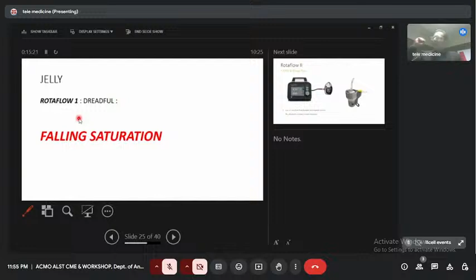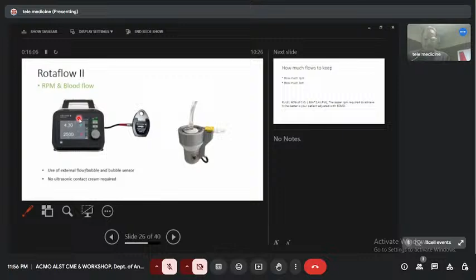is recently used at most of the places, but still, till date, Rotaflow 1 and that previous Cardiohelp is also used. But from now onwards, most centers will have this Rotaflow 2. It has this external flow or bubble sensor and detector that helps us to read the flow of the blood. It doesn't need that jelly part. So they have innovated a new technique so that if the jelly is exhausted, there is no jelly, the patient won't die, right? But again, the jelly is an important component because in 70% of the setups, you will find Rotaflow 1.